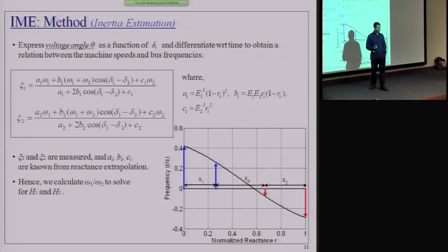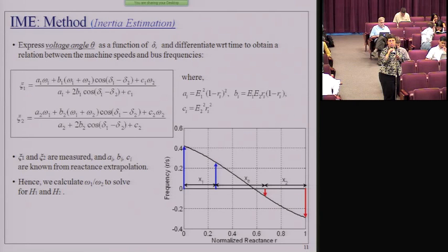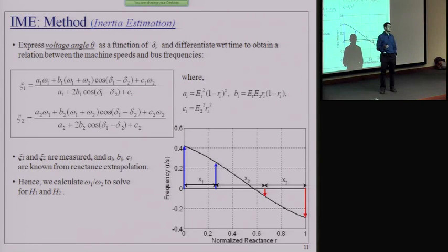So if I lowered the measurement rate, would the interpolation and estimation suffer? As long as you are trying to identify the inter-area dynamics, which typically for the West Coast power system is in the range of 0.4 to 0.6 hertz, and by Shannon's theory you have measurements that cover this bandwidth, then you're fine.